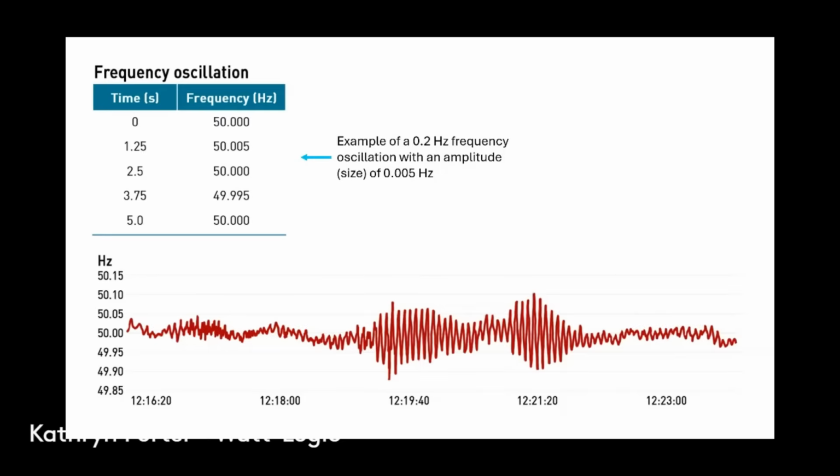And its response to the drop in voltage was pretty much to employ static measures. Now, to begin with, those static measures appeared to work. The oscillations damped, and they took almost 5 minutes to damp in the first instance, but they were damped. However, a few minutes later, they reappeared, and when they reappeared, REE just wasn't able to respond effectively.